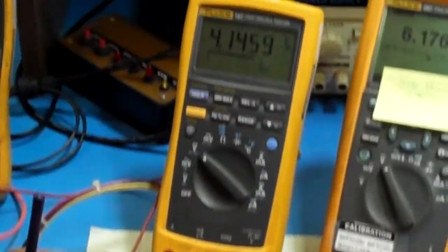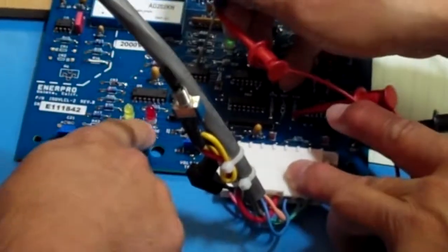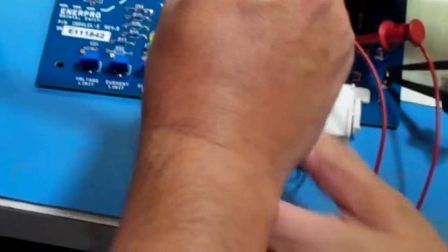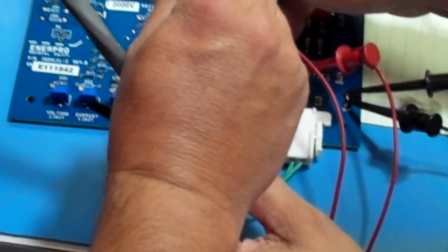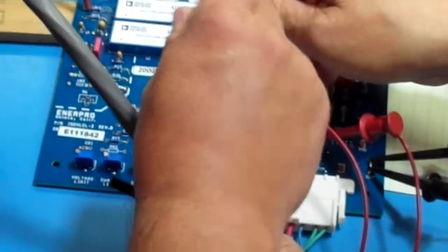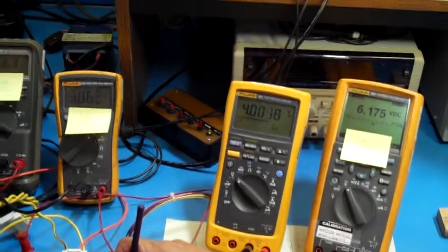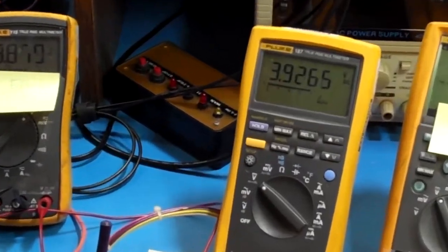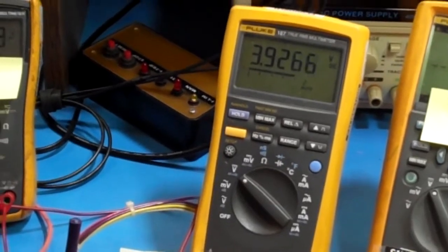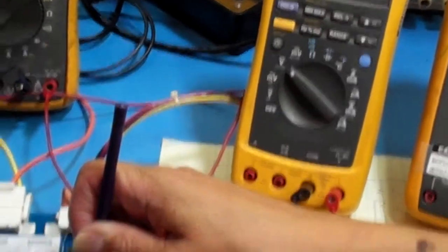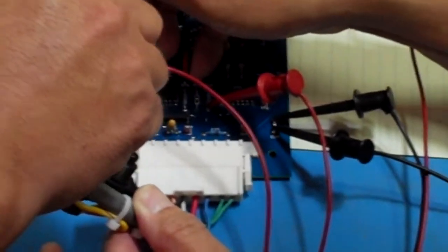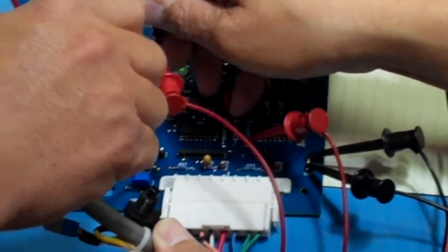If I take my screwdriver, go to the voltage trip, and try to make this equal, first of all, there's no over voltage or voltage trip condition. I'm going to start coming down, see the potentiometer. And I'm going to concentrate on 3.9, so it's going to come pretty soon. I'm going to concentrate here on that LED. There you go. Now I have a condition.